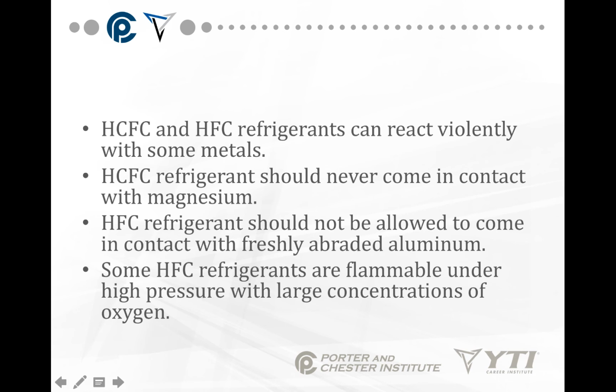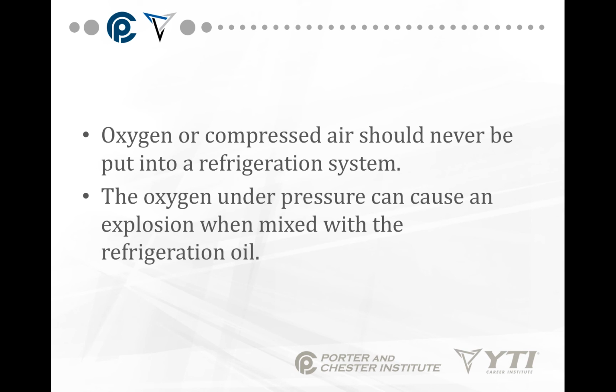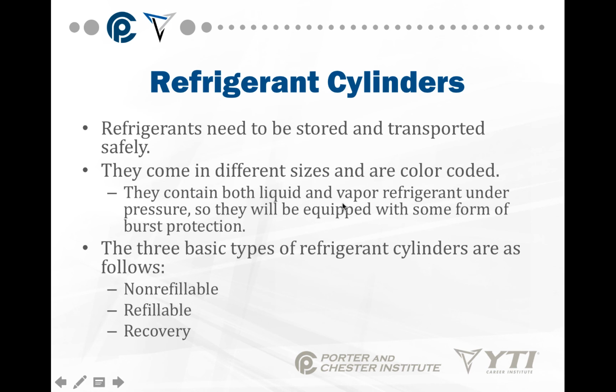Okay. HCFC and HFCs can react violently with some metals. They should never come in contact with magnesium. HFC refrigerants should not be allowed to come in contact with freshly abraded aluminum. Some HCFC refrigerants are flammable under high pressure with large concentrations of oxygen. Oxygen or compressed air should never be put into a refrigeration system. The oxygen under pressure can cause an explosion when mixed with the refrigeration oil. So that is why we only pressure check with nitrogen. We never pressure check with oxygen or compressed air.